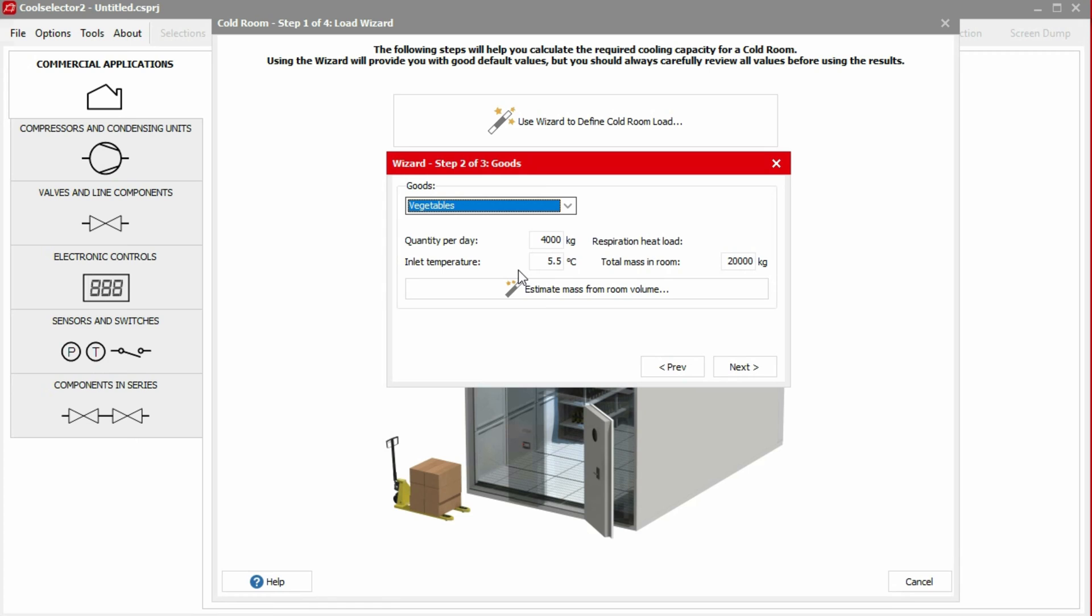Based on this data, the wizard will calculate the cooling load required to cool down the goods from the inlet temperature to the desired temperature in the cold room. Please note that the total mass in the room is required only for the goods which are respiring, such as vegetables and fruits. Since in that case, the respiration heat load should be added to the load.